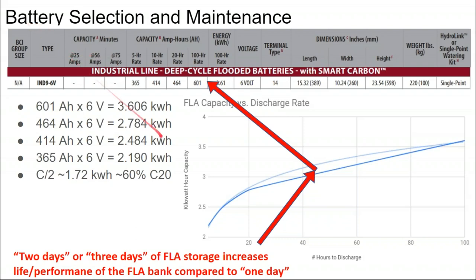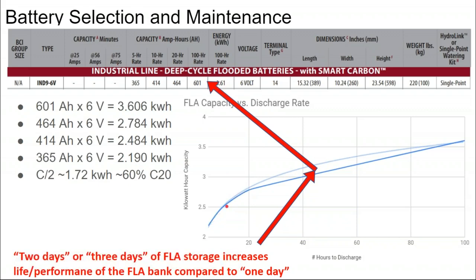The real danger with lead acid is when your battery bank starts to get smaller than a day's worth of electricity, and yet you're still trying to provide whole house backup power, you start getting into this slope between the 20-hour discharge rate versus the 10-hour or 6-hour discharge rate versus anything less than that. You start sliding off the edge of the cliff.